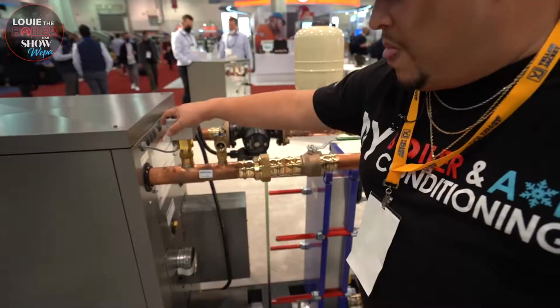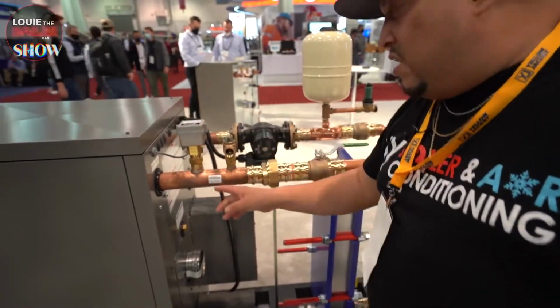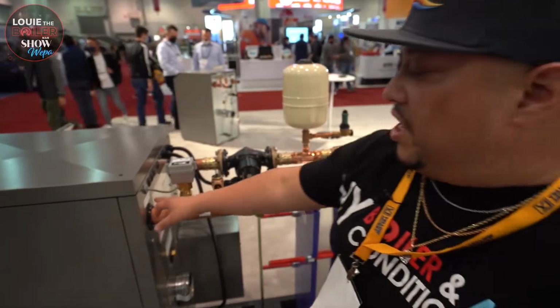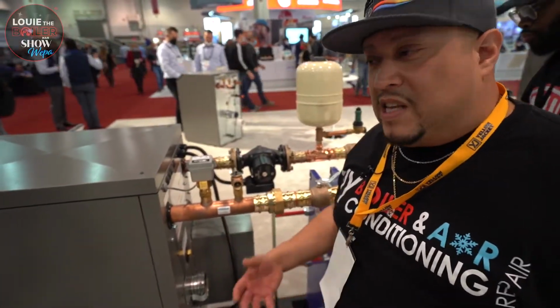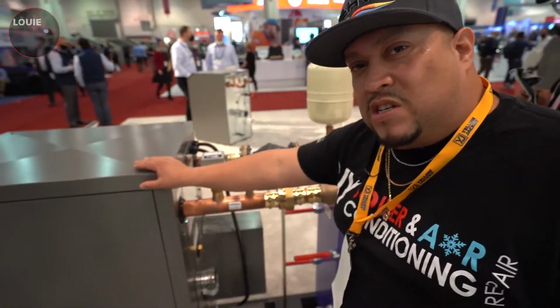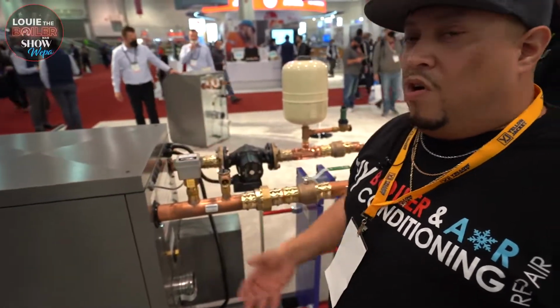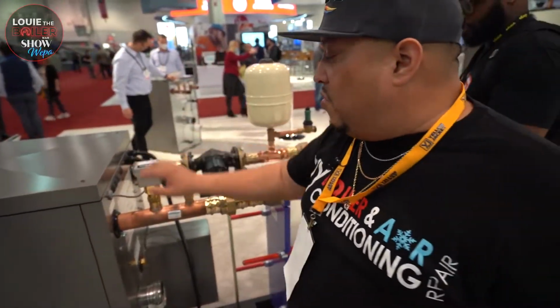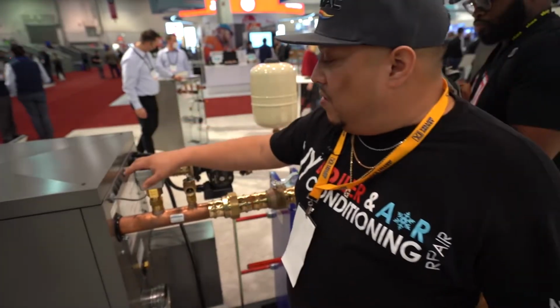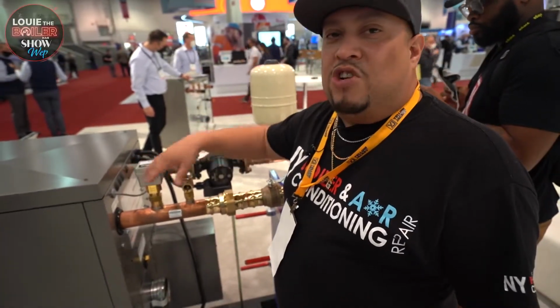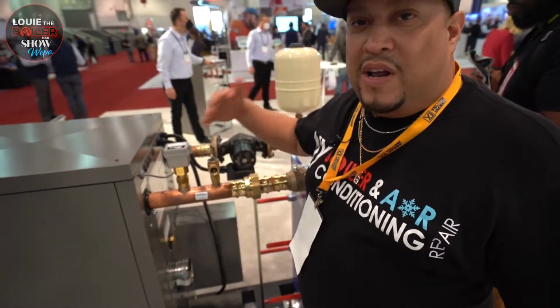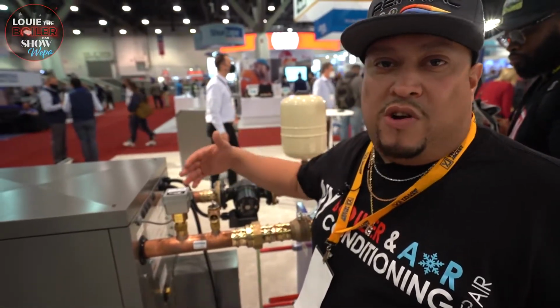A flow switch. Why a flow switch? We want to make sure there's flow of water right here, because we have a heat exchanger, and if you overheat the water, it starts making steam. It's not a steam system, it's a hot water system. And what happens, you can burn out the actual coil. So this just ensures that water is moving. If this doesn't sense any moving water, it's going to shut the system down to protect it from burning itself out or causing a fire or any internal damage.